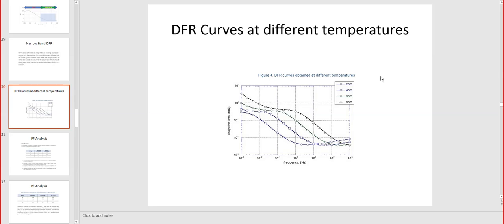DFR curves at different temperatures. So as we said, we want it at 20. As you can see here, the response for dissipation factor, in brackets tangent delta, is actually the bottom line. The lower line only increases at the end, and then we have the same test at 40, 60 and 80. At 80 degrees you can see that the dissipation is the highest. So we can conclude that, at least at low frequency under 10 hertz, the temperature creates larger dissipation. Then higher than 10 hertz, from 10 to 1000, they are in the same range, and we cannot conclude that the temperature brings it up. It actually lowers, so a little bit lower than at 20 degrees.